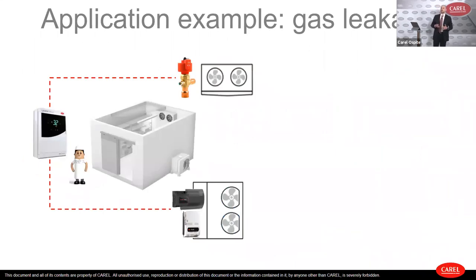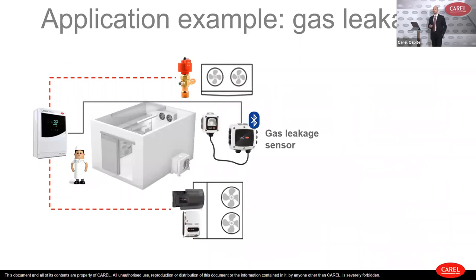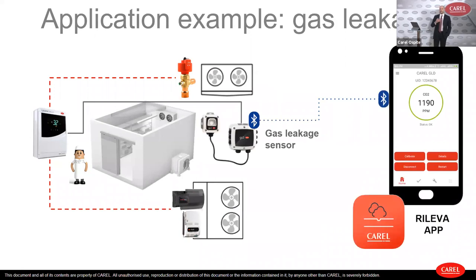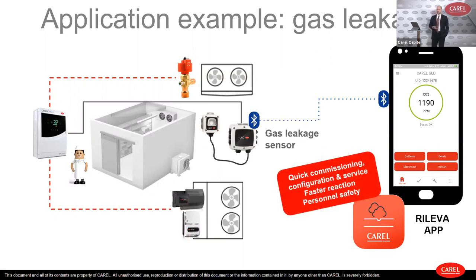Starting from this system, since we care about the environment, let's speak about gas leakage. The new GLD from CAREL with Bluetooth connectivity can speed up all procedures for the installer regarding commissioning and setup, thanks to the new CAREL app — Rileva — which is free on the App Store. You can connect directly to your gas leakage detector for maintenance, setup, and so on.